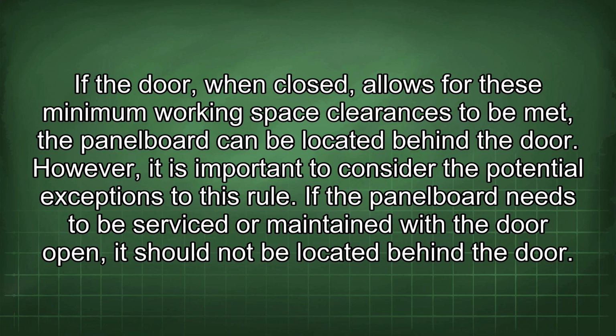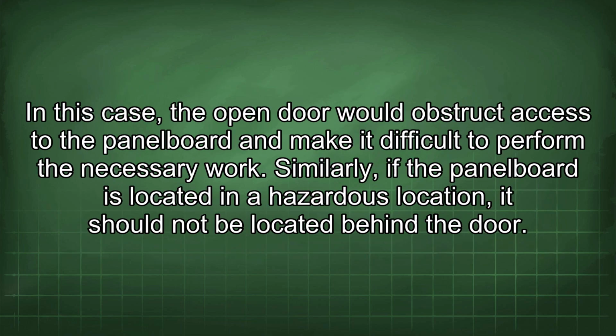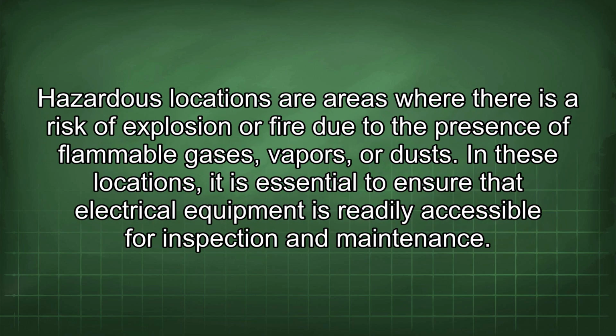If the panel board needs to be serviced or maintained with the door open, it should not be located behind the door. In this case, the open door would obstruct access to the panel board and make it difficult to perform the necessary work. Similarly, if the panel board is located in a hazardous location, it should not be located behind the door. Hazardous locations are areas where there is a risk of explosion or fire due to the presence of flammable gases, vapors, or dusts. In these locations, it is essential to ensure that electrical equipment is readily accessible for inspection and maintenance.